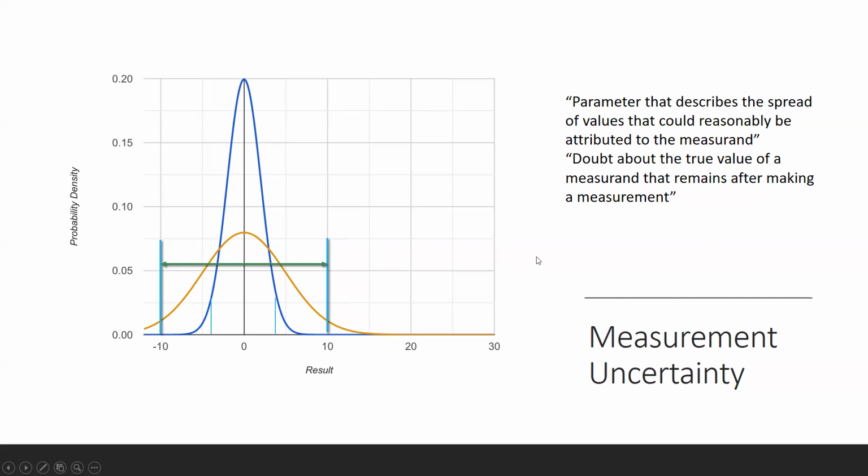So measurement uncertainty calculations will again give you a standard deviation around the result, and you're supposed to take all the components of uncertainty within this. So not just analytical imprecision. If analytical imprecision is here as the blue normal distribution curve, measurement uncertainty would be wider than this.